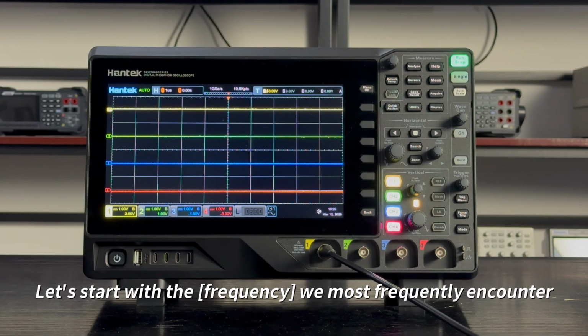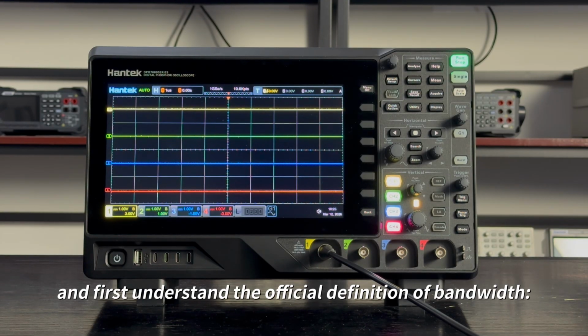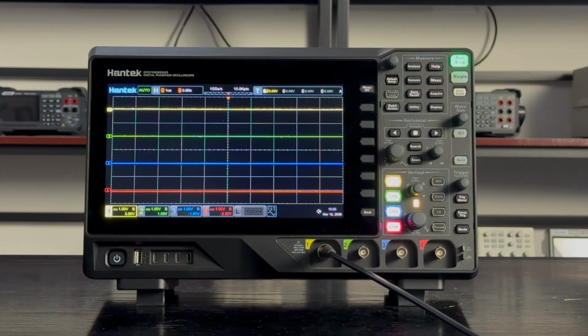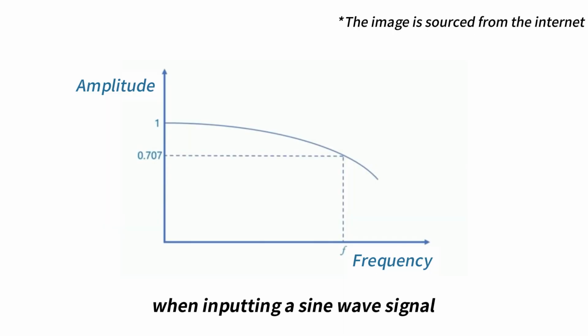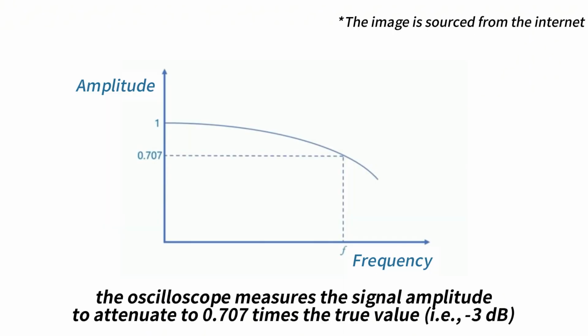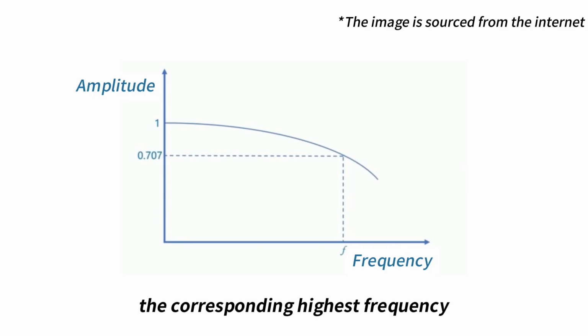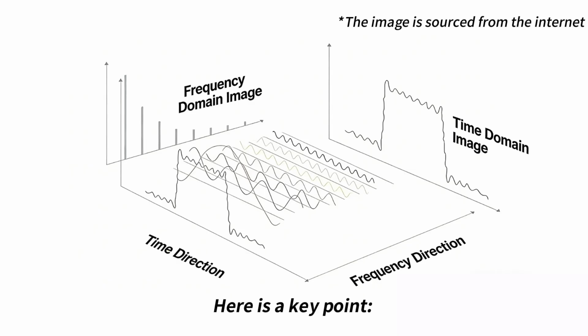Let's start with the frequency we most frequently encounter, and first understand the official definition of bandwidth. When inputting a sine wave signal, the oscilloscope measures the signal amplitude to attenuate to 0.707 times the true value, the corresponding highest frequency. Here is a key point.